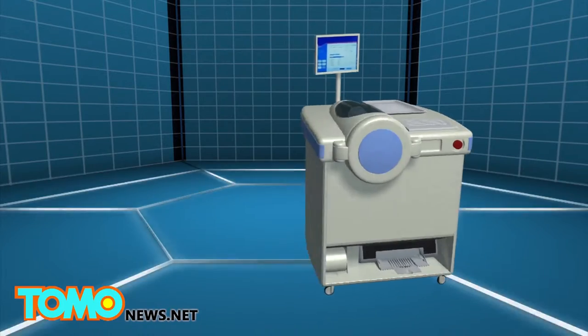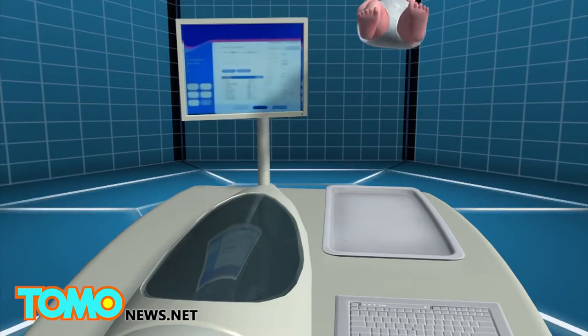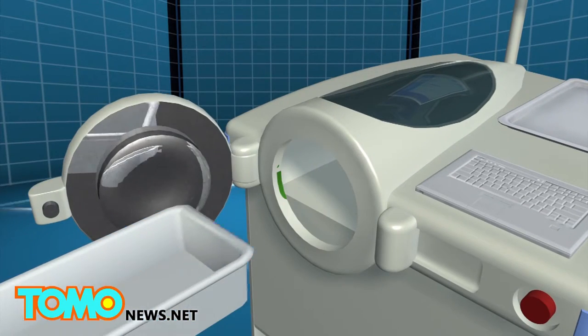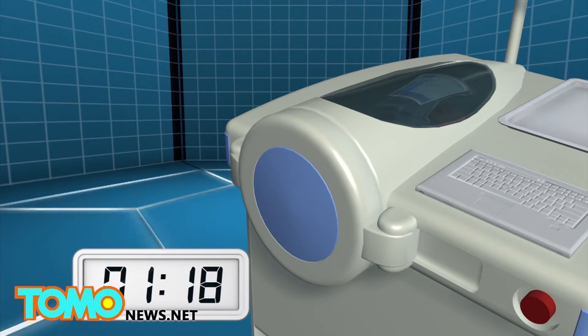The Peapod is a medical device that uses air displacement technology to measure the body composition of premature infants. The baby is first weighed by the device's scale, then placed in an enclosed heated chamber for approximately 2 minutes, where its body volume is measured by the amount of air displaced by its body inside the chamber.